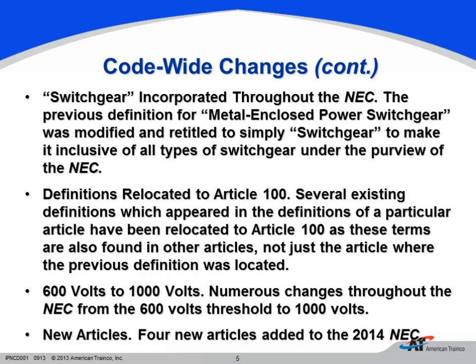At the bottom, you can see we do have 4 new articles added to this 2014 National Electrical Code, so we are going to take a look at those in a minute. Also, we have the 600 volt has been raised to 1,000 volts, and many changes on that in the code book. They did assign a high voltage task group, so the code making panels had a committee to go ahead and take a look at raising that up to 1,000 volts, and the reasoning for that is there are many systems that are currently out there between 600 and 1,000 volts that in reality they're still fairly safe, and I want to give you a couple examples of that.